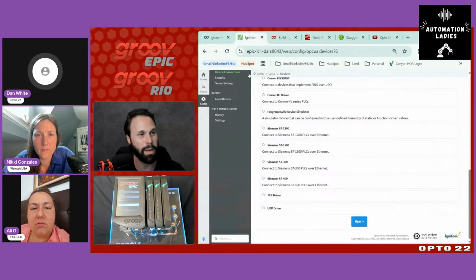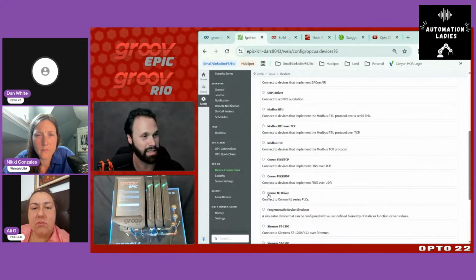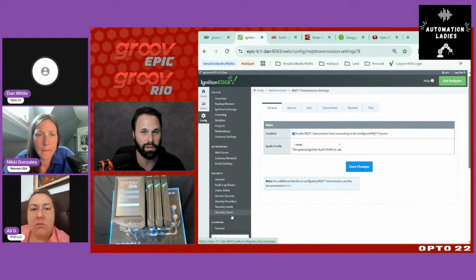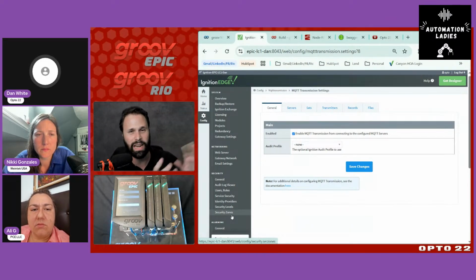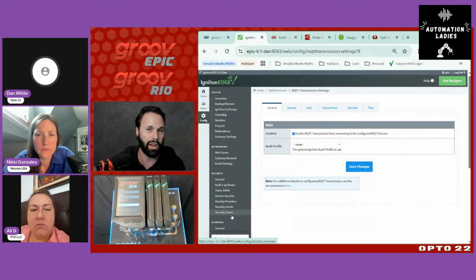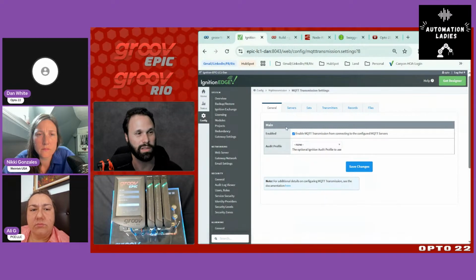Maybe the third reason is, if you're just using a GRV-EPIC and you don't have all these third-party devices, but you want to do some MQTT communication, yes, we have a native driver on here, but Ignition's MQTT transmission module allows you to publish various different data sets to various different MQTT brokers. So I can say I want data A, B, and C going over here, data D, E, and F going there, and data X, Y, Z going there. Ours is more of a one-to-one, not quite so feature rich. So that's a lot of what I see: data redundancy, connecting third-party PLCs, or really taking advantage of this rich MQTT distributor module at the edge.